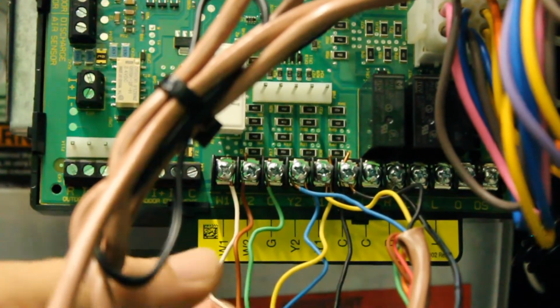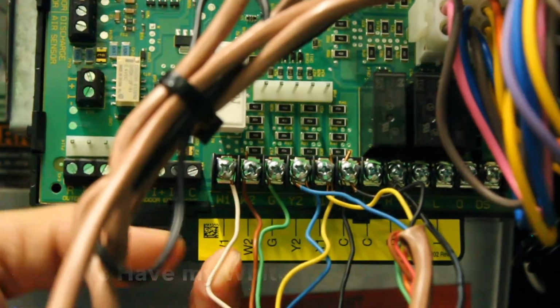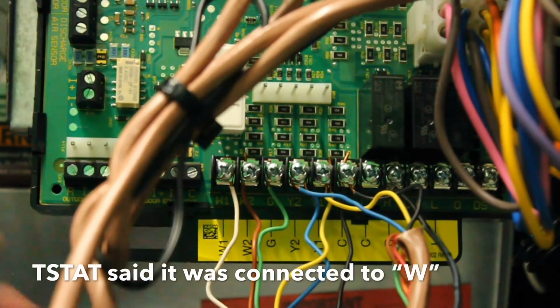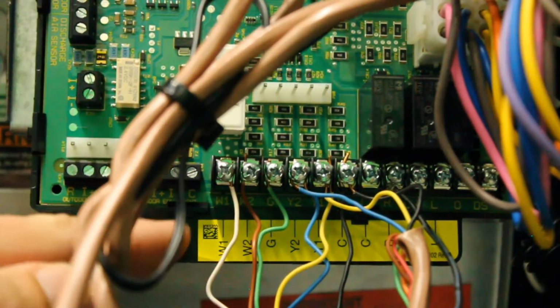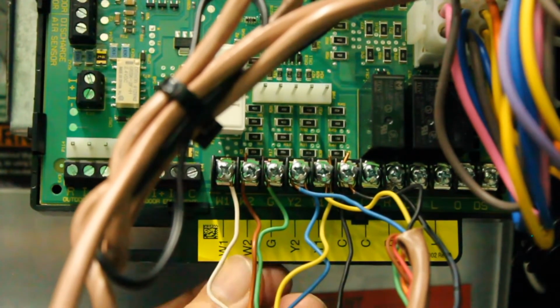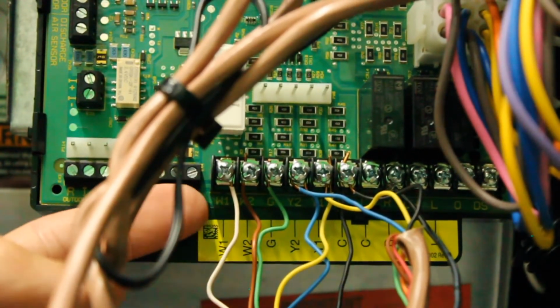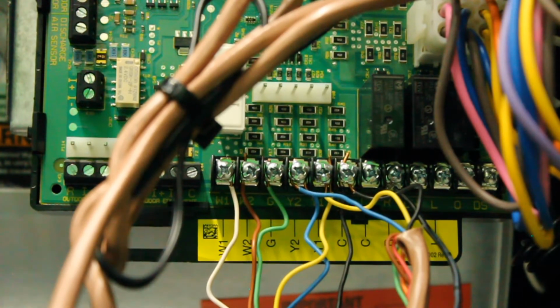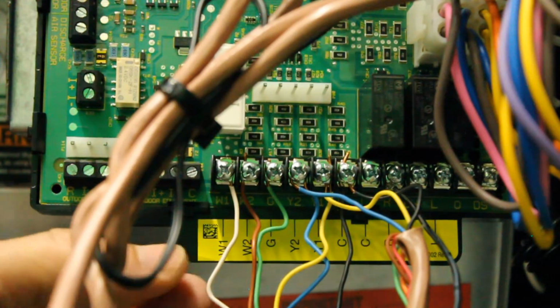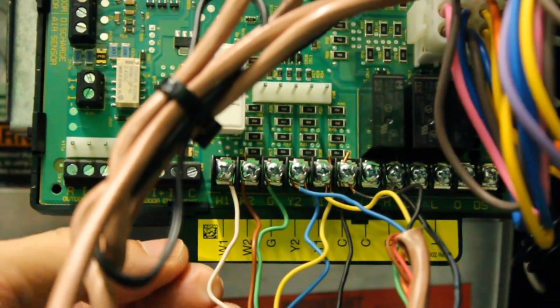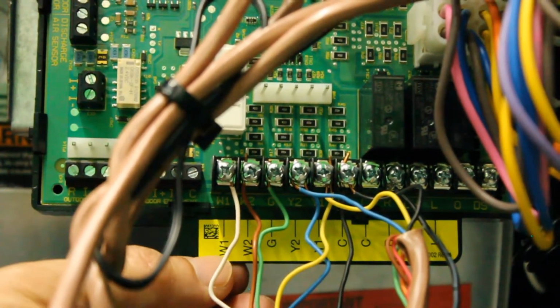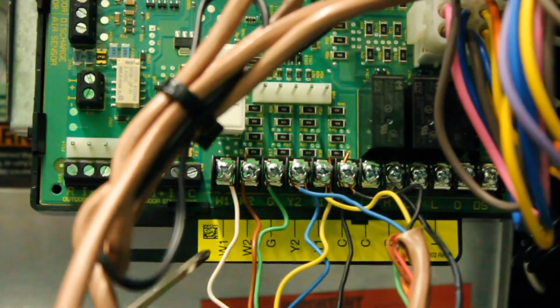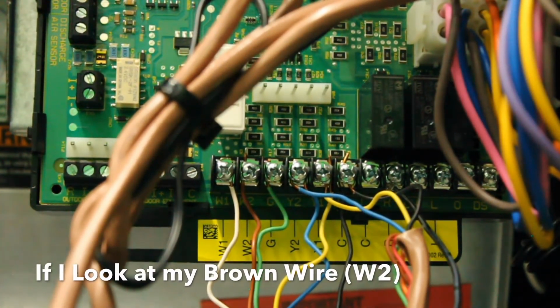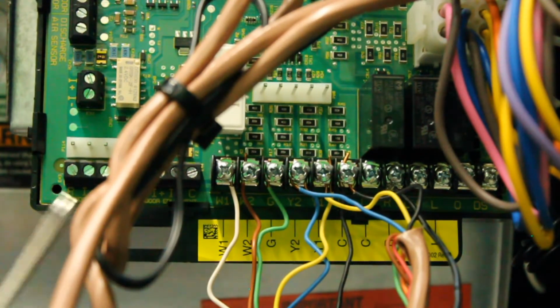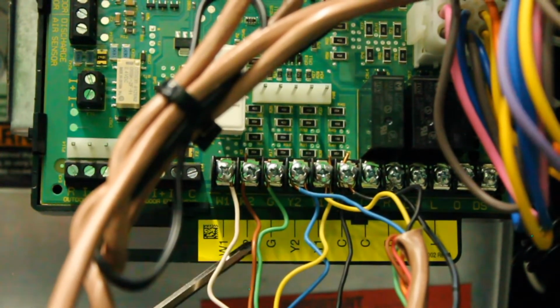So if I'm looking at it with the thermostat, I have my white wire, which on the thermostat was connected to W. On the board, these terminals are identified down here in this yellow tab. Some are actually on the control board, so they're different variations. Again, make sure we don't have power to the system. The white wire is my first stage heat. It's connected to the thermostat on W. It goes to W1 on the board. If I look at my brown wire, which was connected to W2 on the thermostat, it goes to W2 on the board, the brown wire.